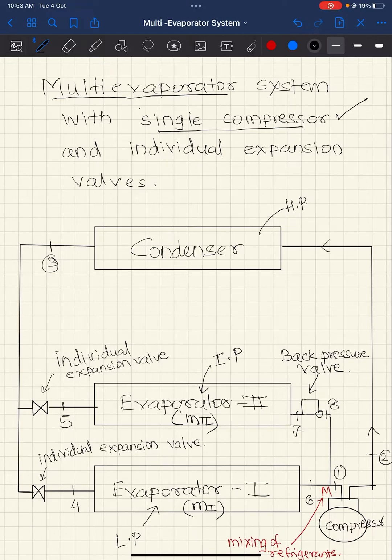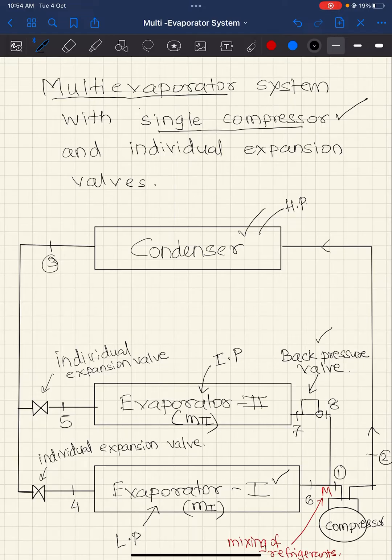The compressor operates between the lowest pressure (evaporator one pressure) and the highest pressure (condenser pressure). We need to think of an idea of lowering the pressure of evaporator two and bringing that refrigerant to the lowest pressure. For that, a back pressure valve is provided, which throttles the refrigerant coming out of evaporator two. Mixing then happens at point M, where refrigerant of mass m1 from evaporator one and mass m2 from evaporator two combine.